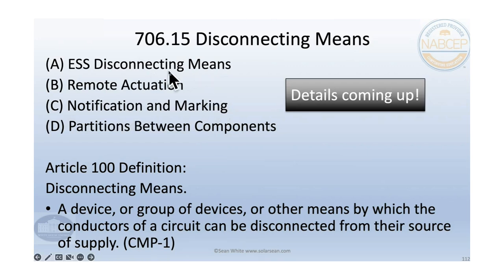Disconnecting means. So we are going to talk about some of the stuff on disconnecting means, and we're going to look into that a little bit. This is just kind of a summary of what's coming up, but we're going to have different types of disconnecting means too. We have the PV system disconnecting means, and that needs to be load break rated and things like that when we're talking about PV. But we also have equipment disconnecting means too. And so most of Article 706 is talking about the energy storage system disconnecting means.